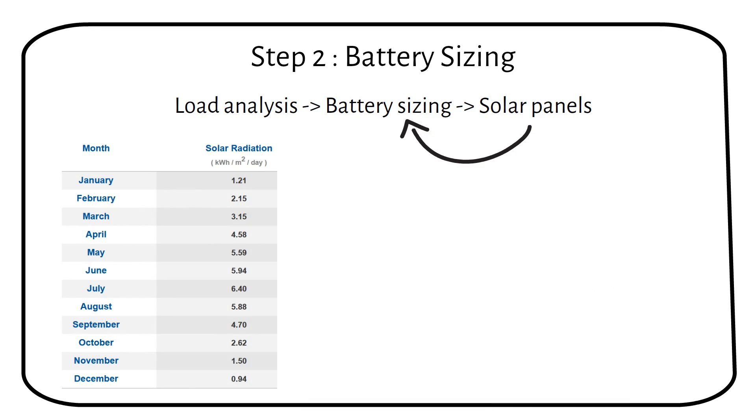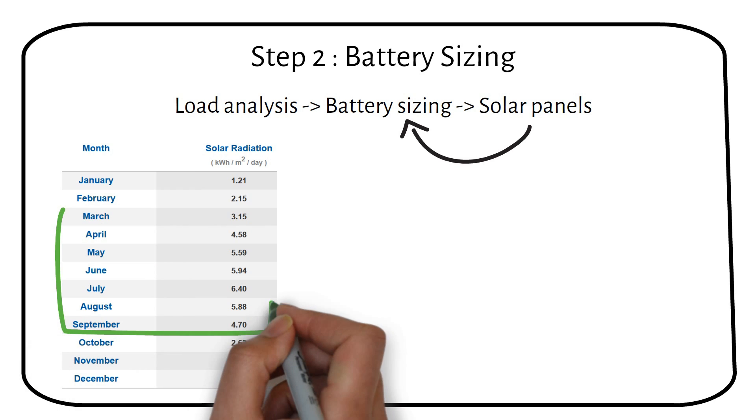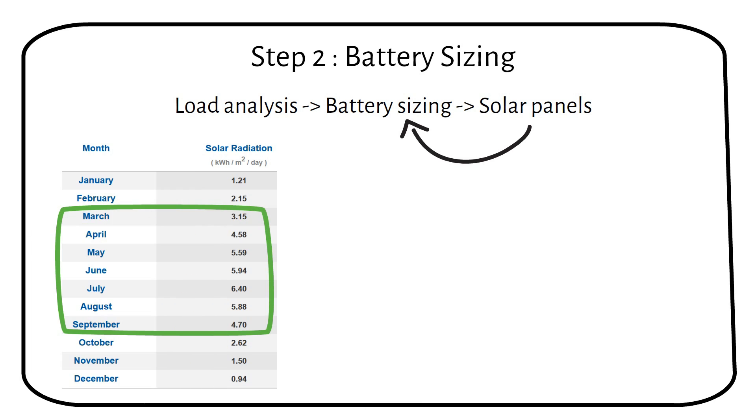When we look at the sun hours for Vancouver, we can see that we have several months over 3 sun hours. For the months without 3 sun hours, we will use a generator to recharge the battery. Using a generator will be cheaper than designing the system for a minimum of 1 sun hour in December. So we will work with 3 sun hours.